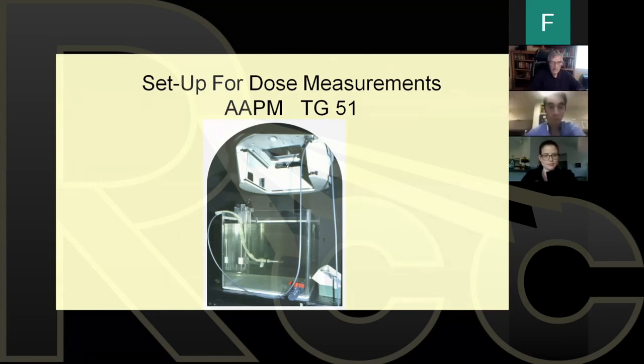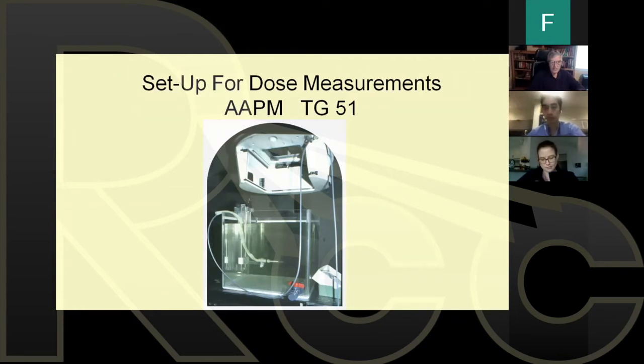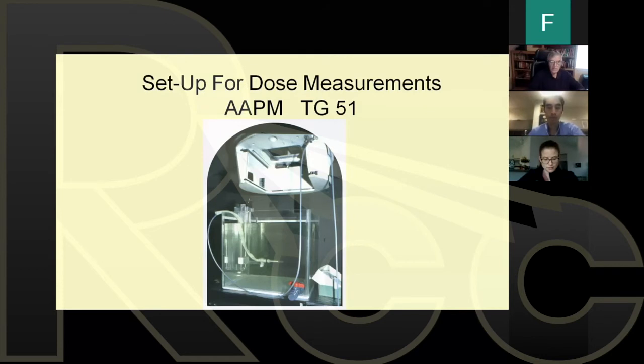If an engineer comes in and changes certain key components of the machine, it's so important to recheck the calibration of the machine and be sure that the output, the dose per monitor unit, is consistent and hasn't changed. The engineers where I practice in the States never adjust the output of the machine. That's my job. It is the job of the physicist to adjust the output of the linear accelerator.